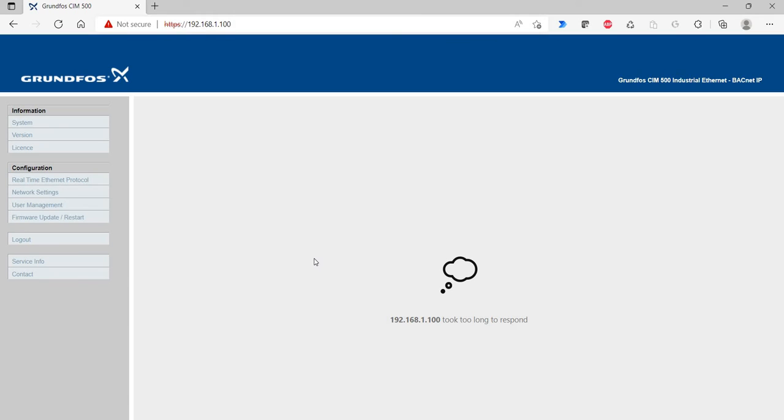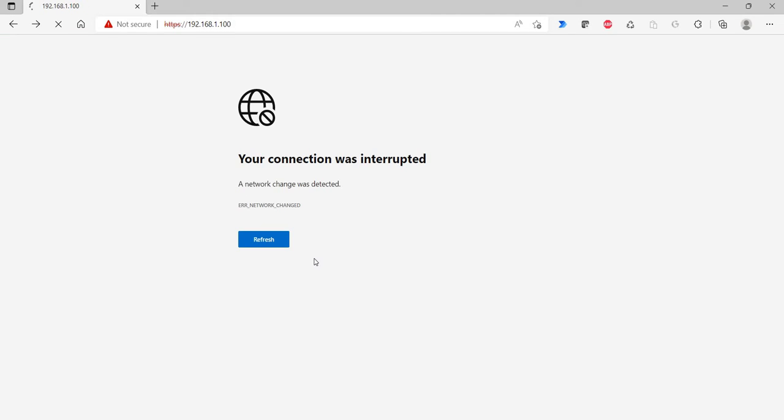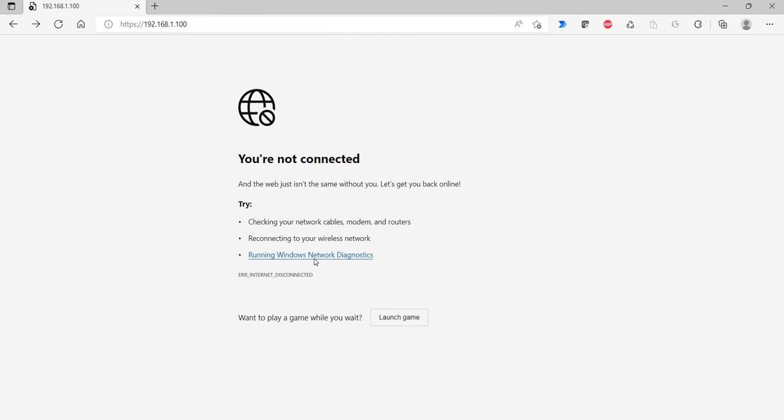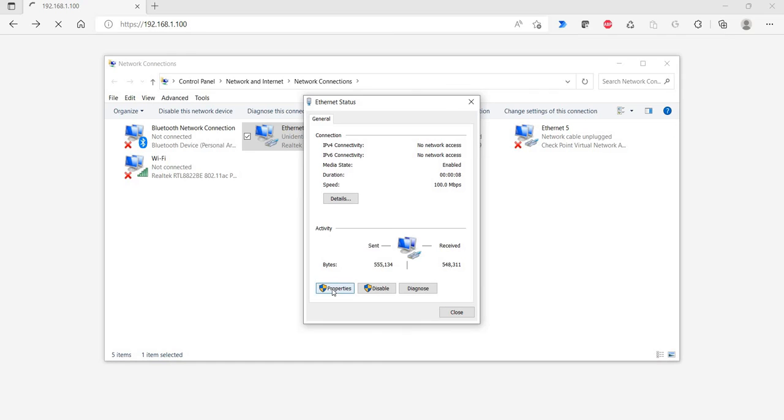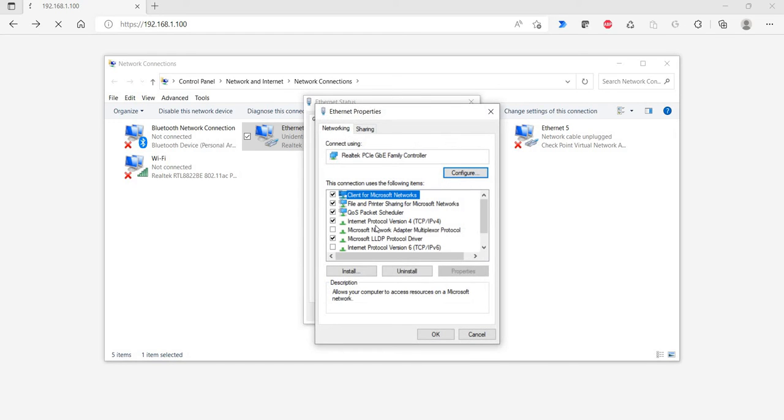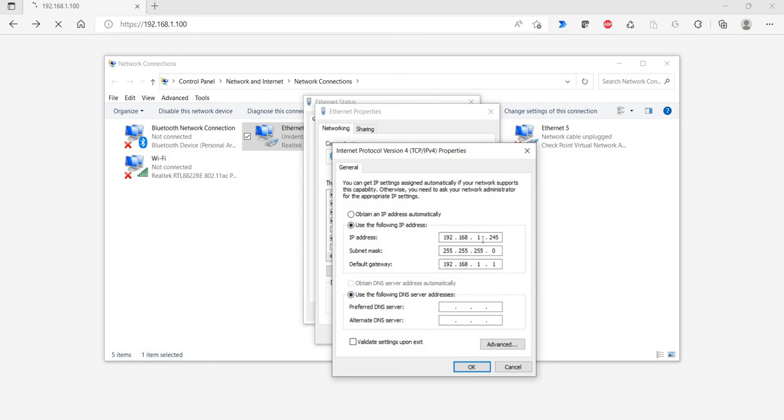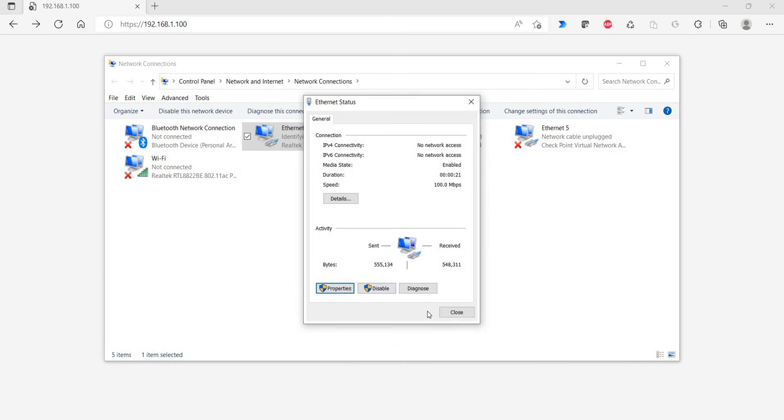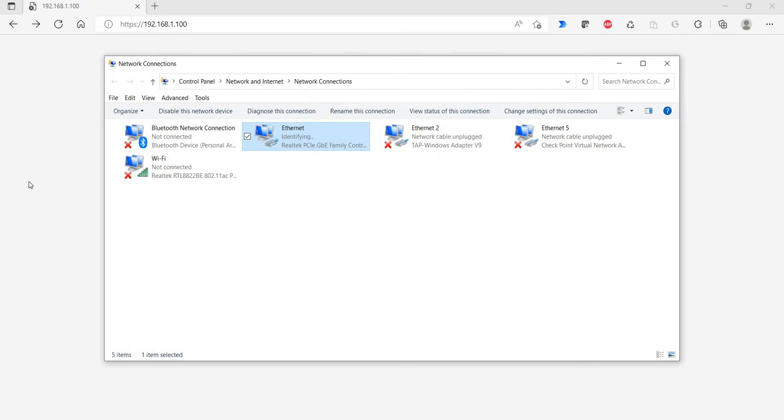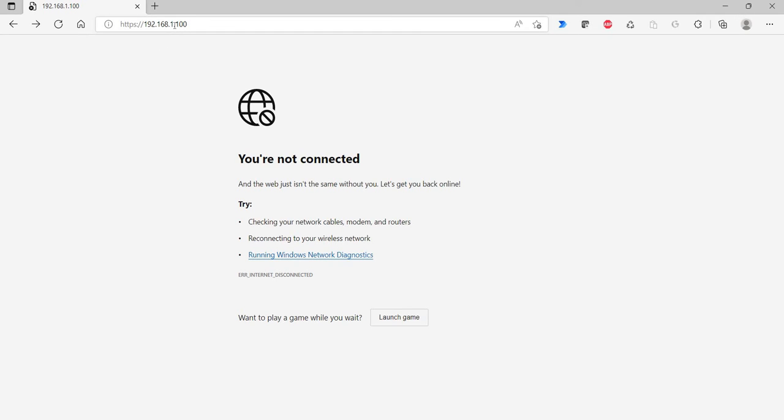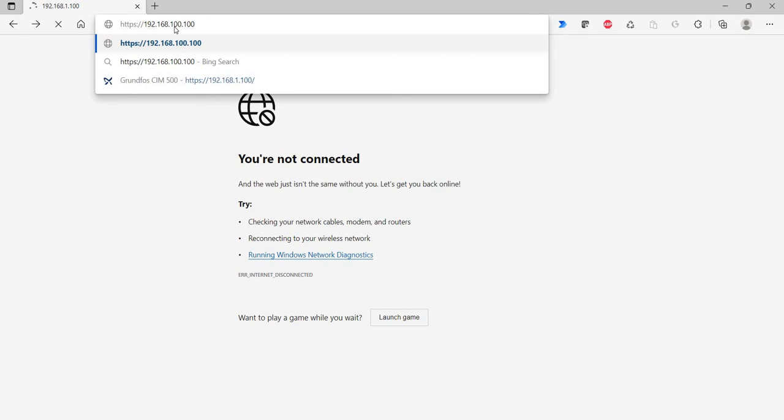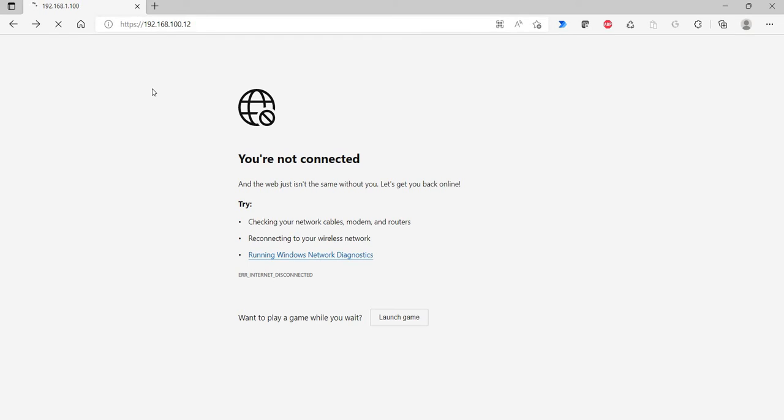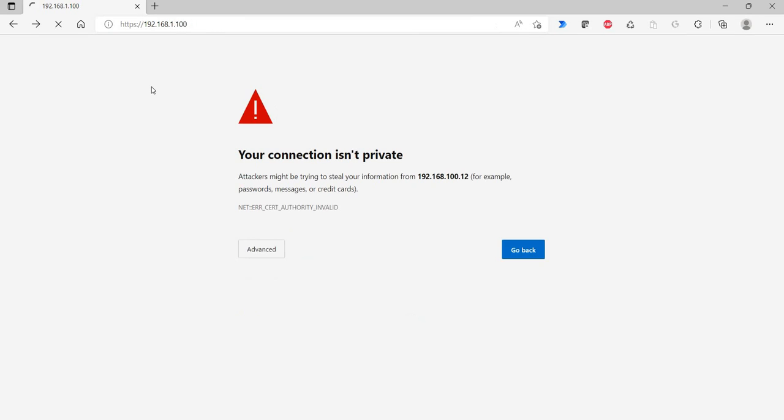So I'm going to unplug my computer from the CIM card and I plug in the ethernet network connection to the CIM card so it's on the BACnet network. So now I'm going to go back into my IPv4 settings, I've connected to the BACnet network now. I'm going to set my computer to be on the network and now if I go into that IP address that I just gave that pump, I can check.